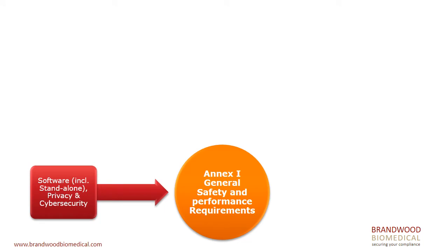Firstly, software. Software, including standalone software, now has its own section in the General Safety and Performance Requirements. And those requirements address things that we already know, so they call upon the software lifecycle standards. So if you're familiar with IEC 62304, the software medical device software lifecycle standard, or the human factors guidances and standards that go along with software, that we know and love and are well familiar with.